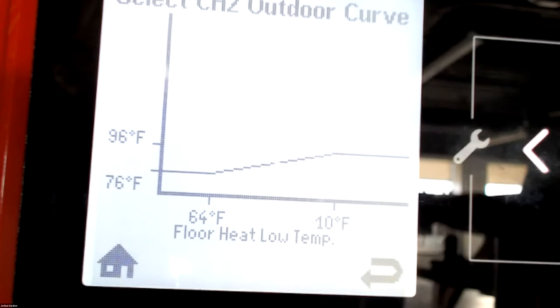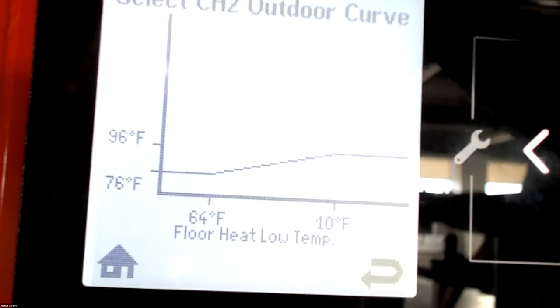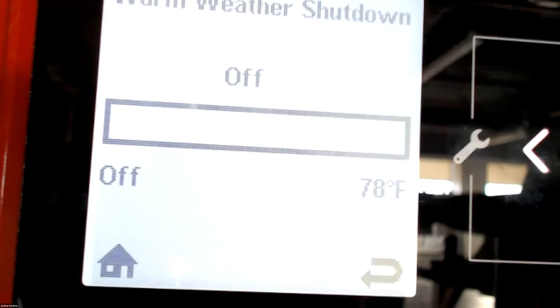So CH2, you got your curve, you just hit the center circle button. Warm weather shutdown. Most cases, you're going to leave this off. It's come from the factory off. Where I see this kind of most popular is with landlords and tenants. Landlord wants this on. He wants the heating system to turn off at 70 degrees outside. You know, maybe he's paying for the fuel. That's kind of where I see this used a lot.